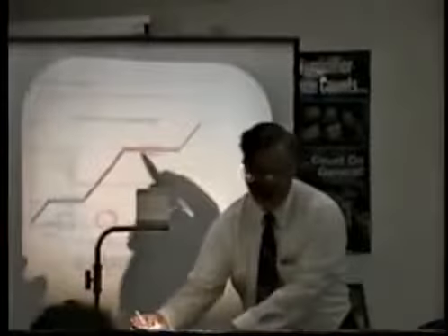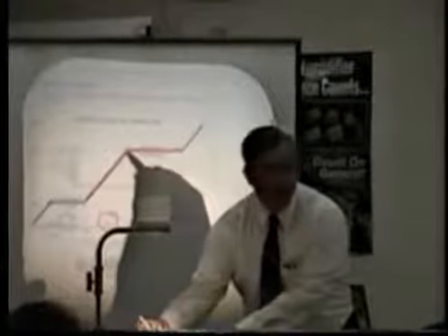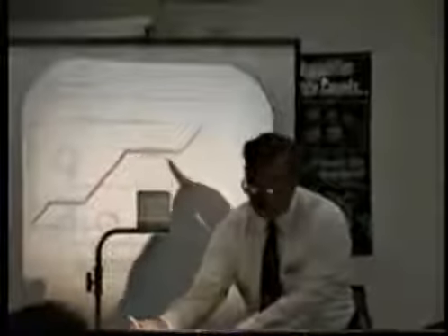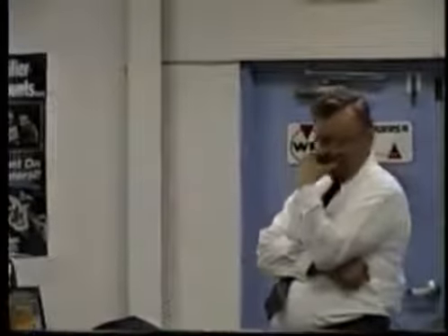How many BTUs does it take to change the state from 212 degree water, and you better understand this one now, to 212 degree steam? It's almost 1,000. It takes the equivalent of burning almost 1,000 wood kitchen matches to convert a pound of water to a pound of steam. Now, I'm leading you somewhere. Pay attention now. No change in temperature. We went from liquid to vapor.